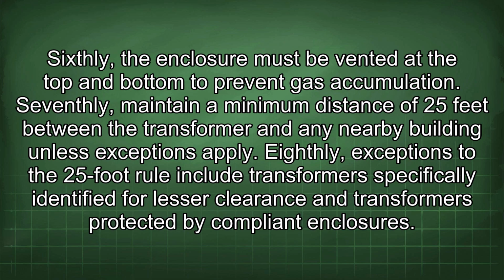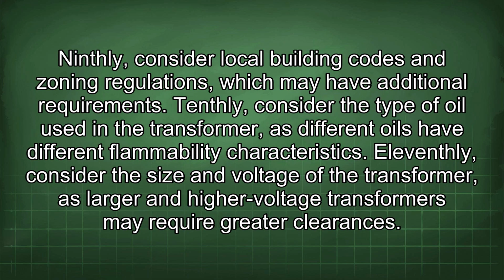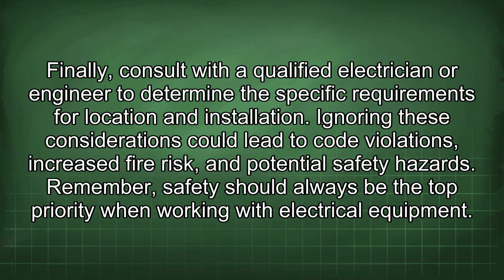Seventhly, maintain a minimum distance of 25 feet between the transformer and any nearby building unless exceptions apply. Eighthly, exceptions to the 25-foot rule include transformers specifically identified for lesser clearance and transformers protected by compliant enclosures. Ninthly, consider local building codes and zoning regulations, which may have additional requirements. Tenthly, consider the type of oil used in the transformer, as different oils have different flammability characteristics. Eleventhly, consider the size and voltage of the transformer, as larger and higher voltage transformers may require greater clearances. Finally, consult with a qualified electrician or engineer to determine the specific requirements for location and installation.